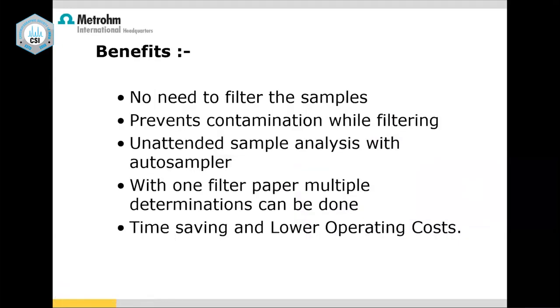How does it benefit you? You don't have to filter the samples yourself. It prevents contamination while filtering. If you have an autosampler, it's unattended, and you don't have to use one filter paper for every sample. With one filter paper, you can filter multiple determinations, at least 15 to 20. So this is definitely time saving, and it leads to lower operating cost.